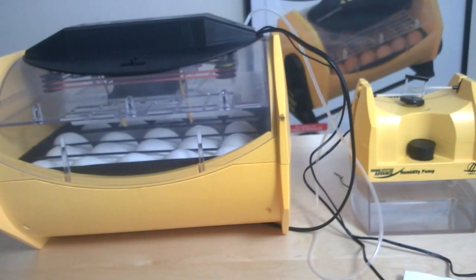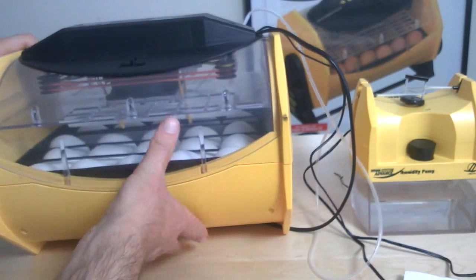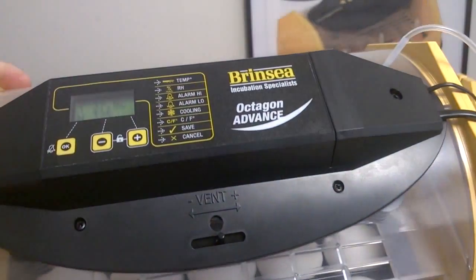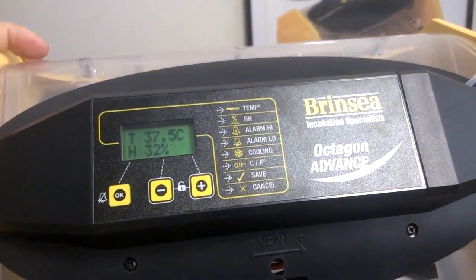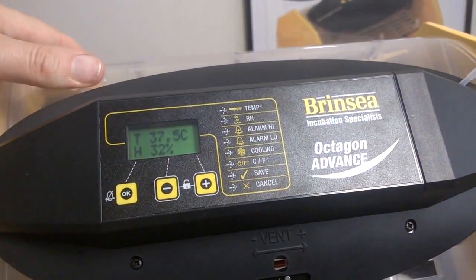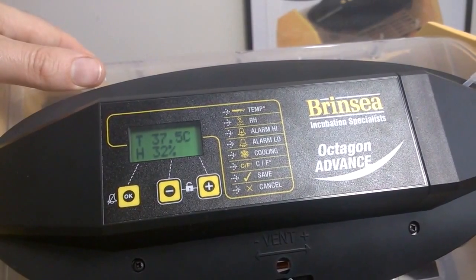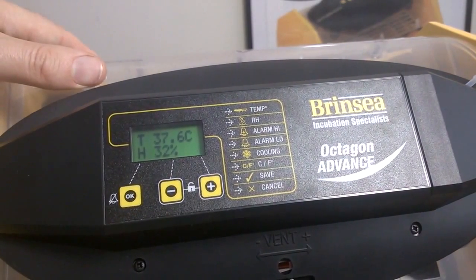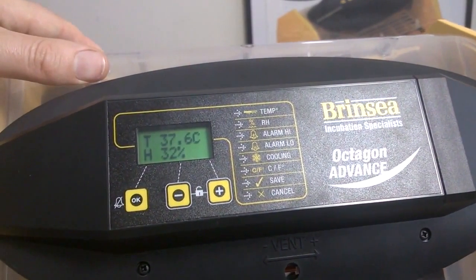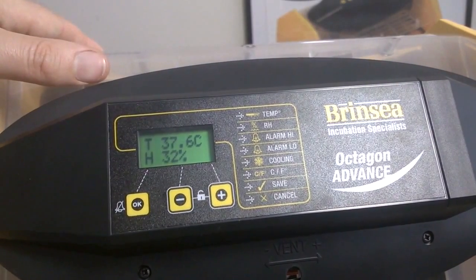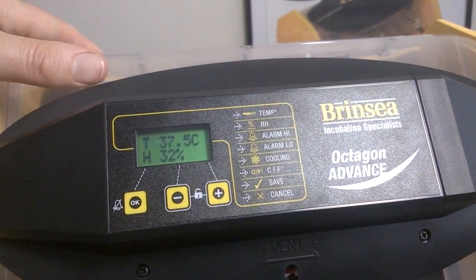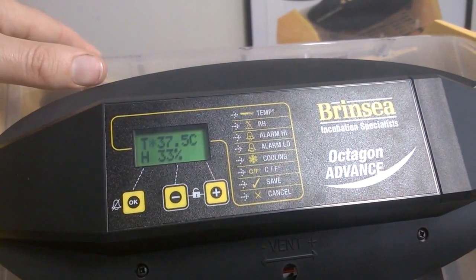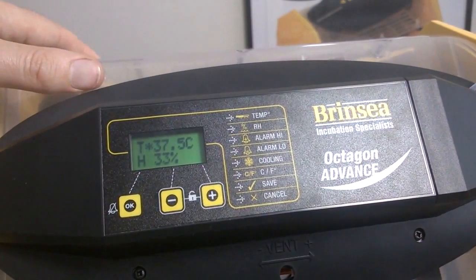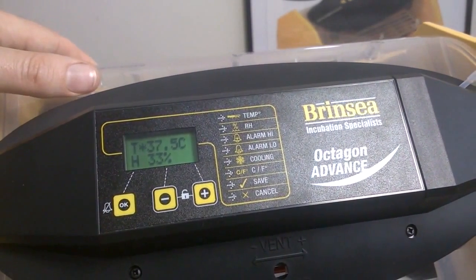Okay, so we've now left this for a good hour to get up to temperature and stabilize a little bit. So let's show you where we're now at with this machine. Hopefully you can see that the temperature is at 37.5, 37.6, rotating around 37.5 as it should be, and the humidity is being indicated as 32%. Now we want that machine up at 40% humidity. That's what I want it to work to.